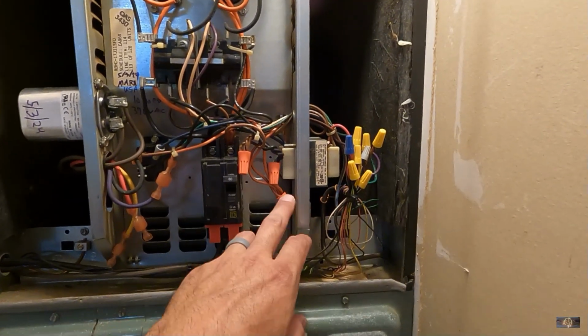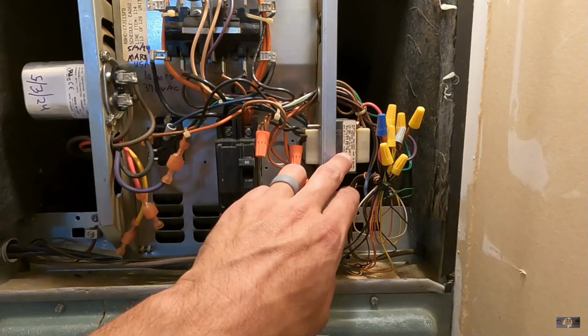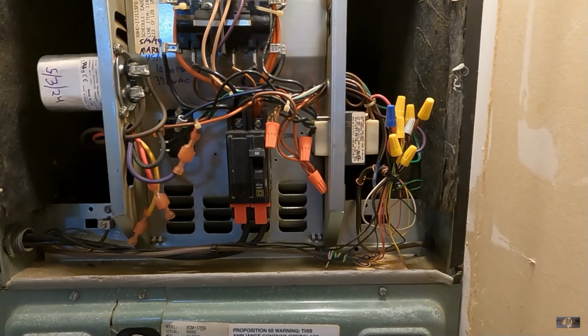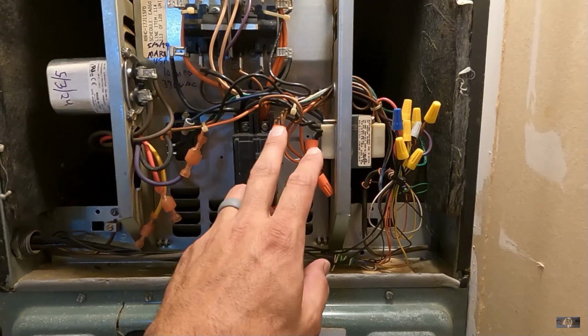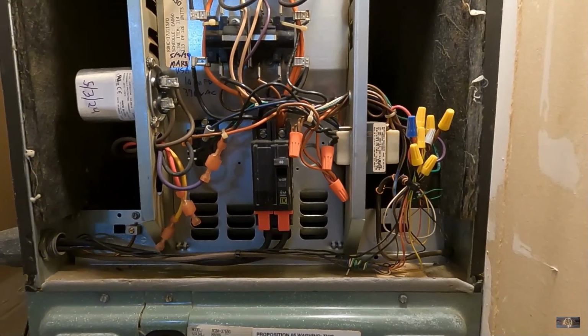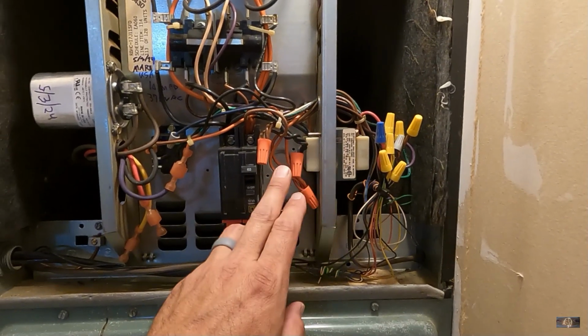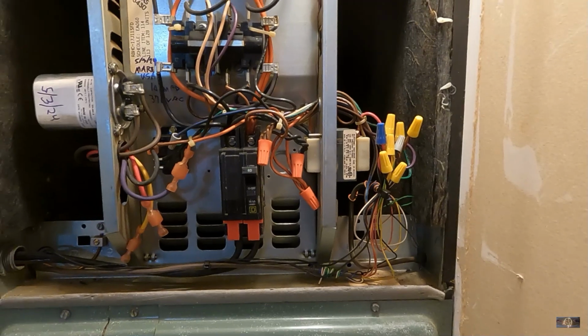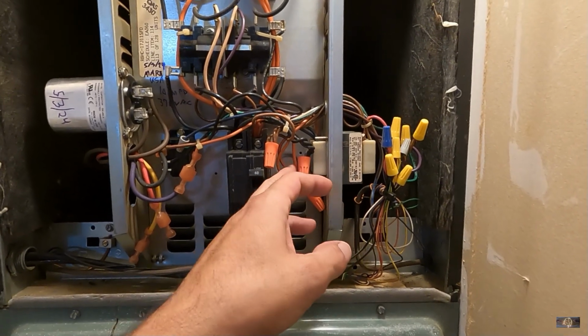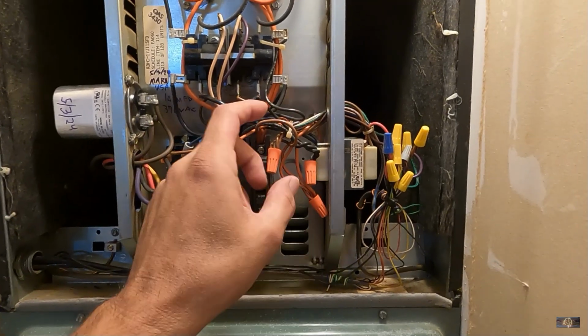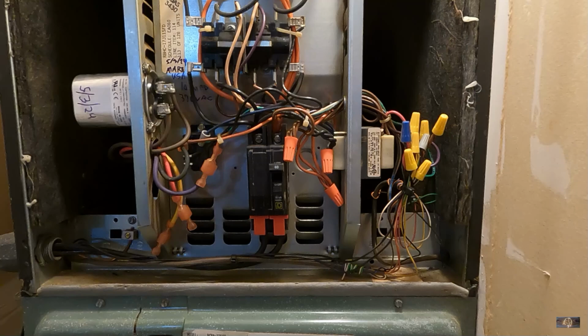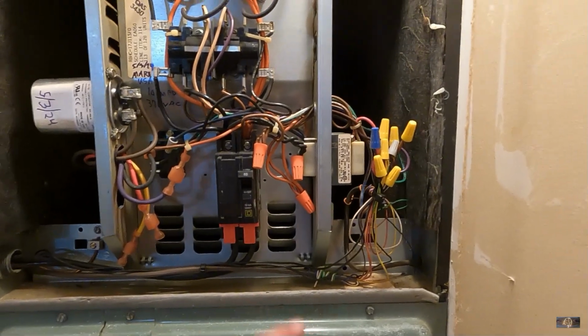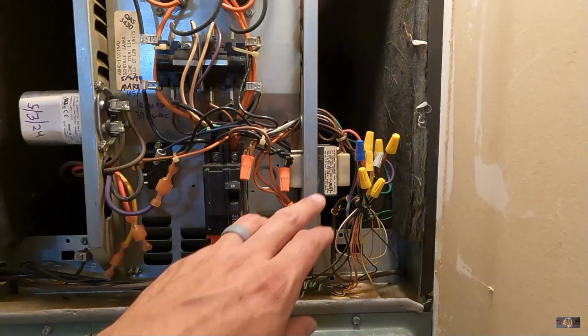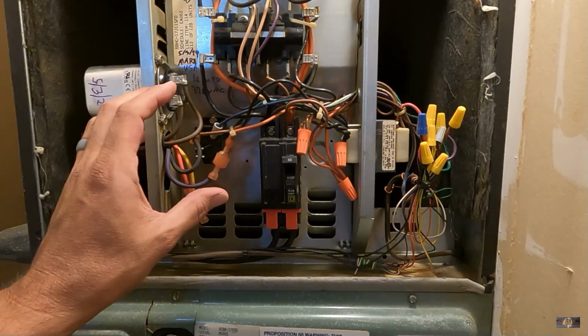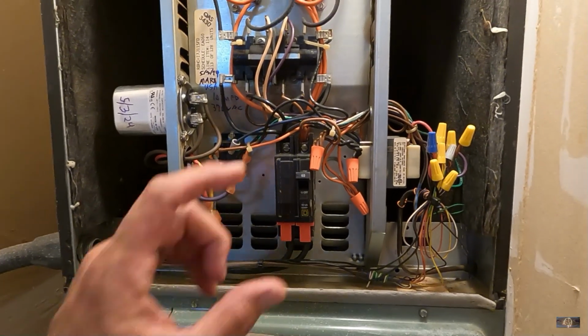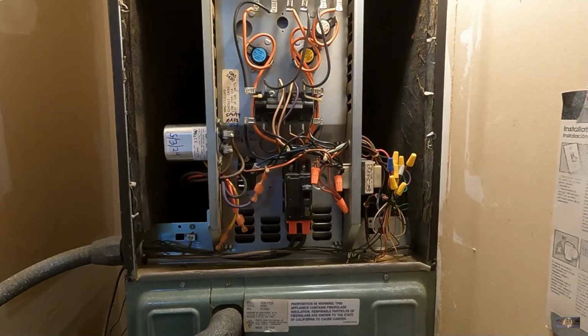So it's something that if you're on these units, you can recommend to the customer, hey, to prevent further damage in the future, if you have a low voltage short situation, let's put an inline fuse in here and help protect that transformer from getting fried. Because that fuse being in line there on the hot wire will definitely protect that transformer. So you just find out which side is your hot side, separate the one line that leads out of it, put the fuse in, and connect the fuse in series with the other wires, and help protect your transformer. So it's a nice upgrade you can do to systems that don't use a typical blower board and are using just a relay. You can put a fuse in and help save the customer some money in the future.